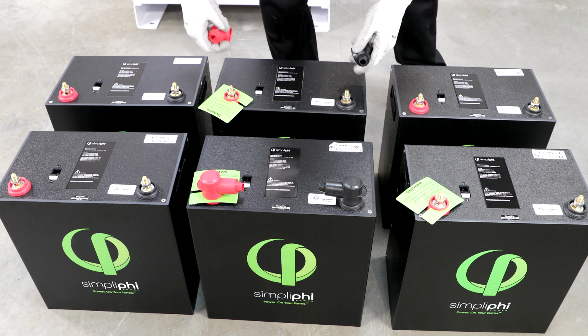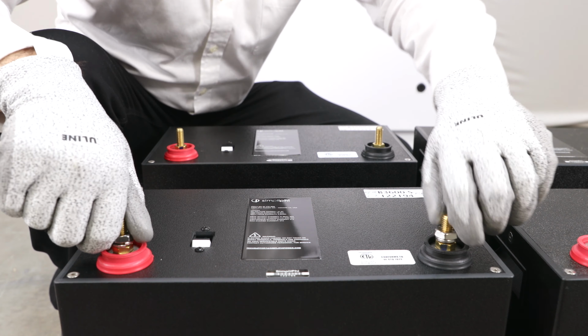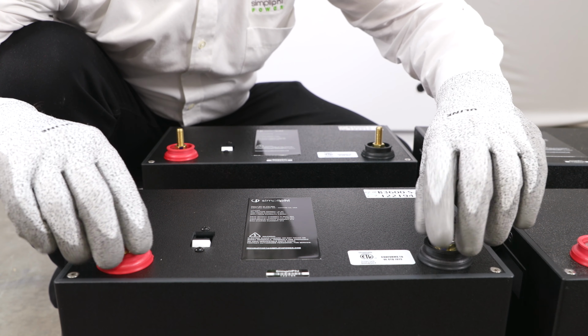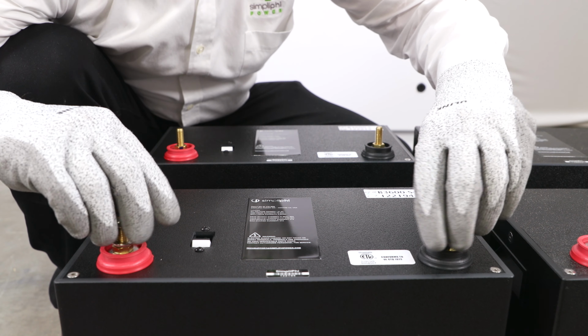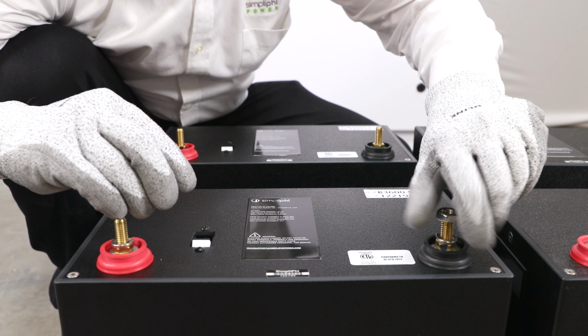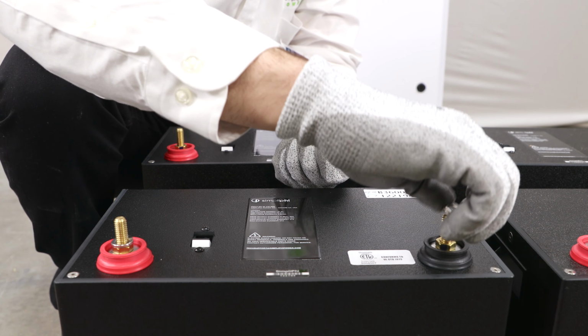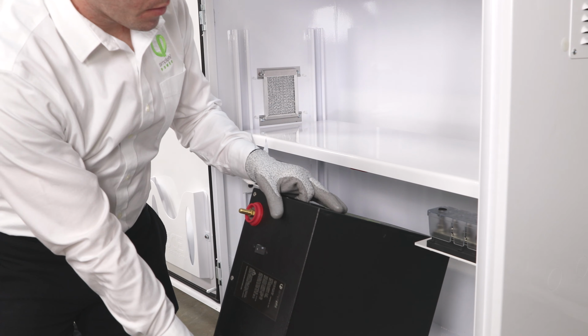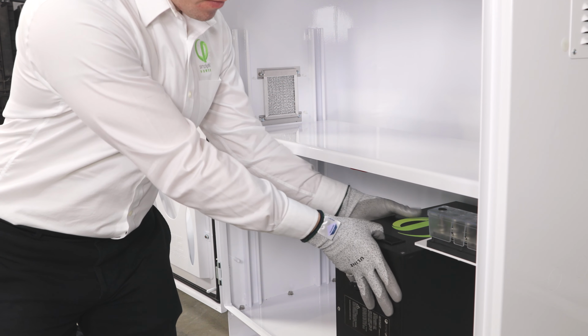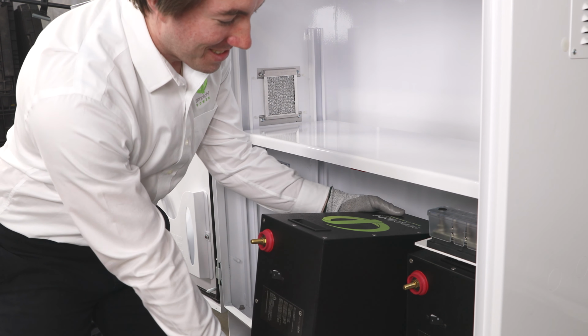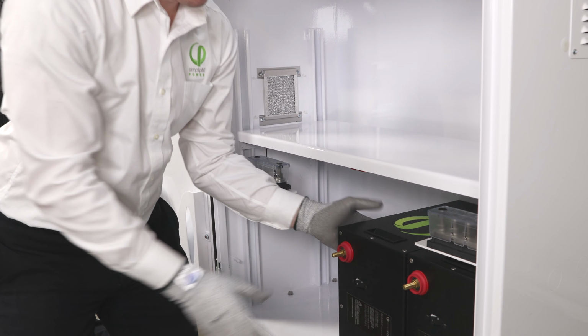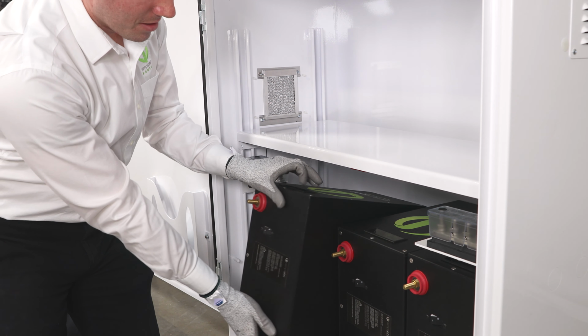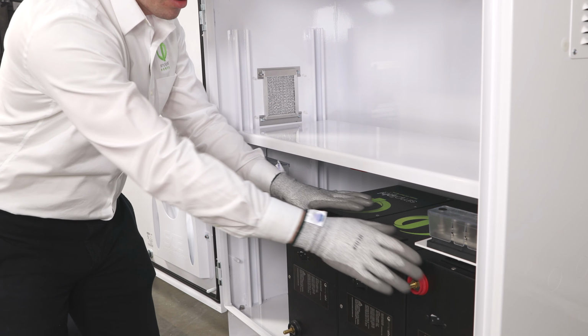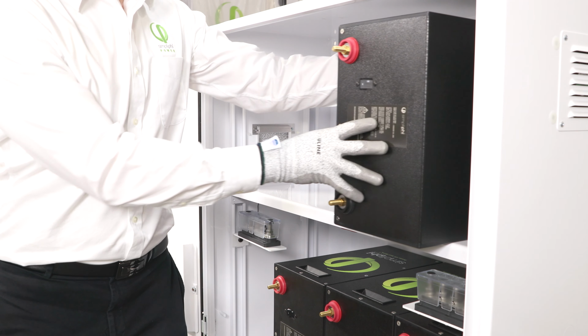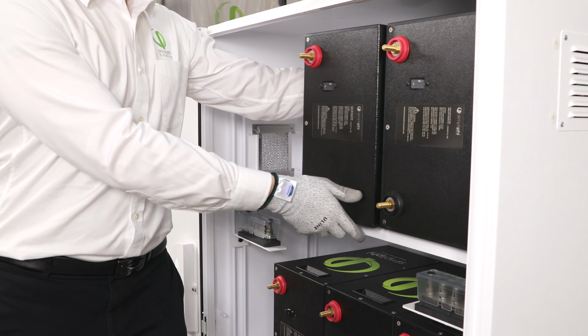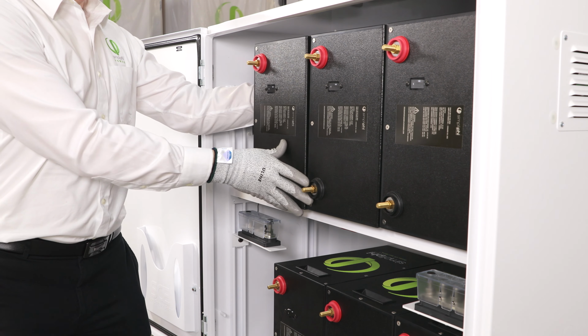Prepare the battery modules for installation by removing all black and red terminal boots, 11/16-inch stainless steel hex nuts, and 3/8-inch lock washers from the battery's terminals and set aside. Begin placing the batteries into the BOSS.6, starting at the bottom of the enclosure. Be sure that the battery terminals point forward toward the door, with the negative posts nearest the bottom of the enclosure. After placing the batteries on the bottom shelf, place the remaining batteries on the top shelf.